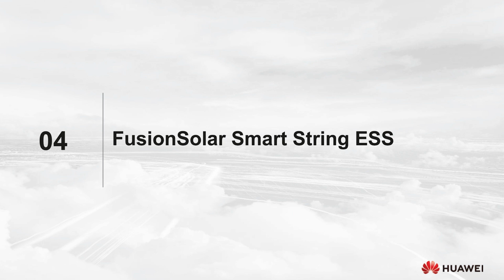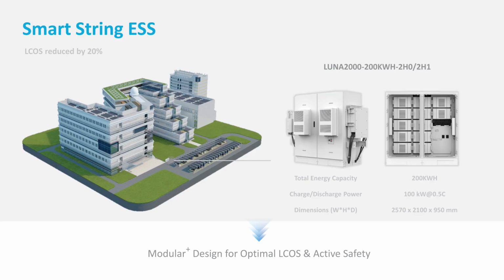Okay, so let's move on to the topic that we are here for today, which is the FusionSolar Smart String ESS. This is a containerized solution. It's 200 kilowatt hours. We call it 200 kilowatt hours, but it's actually 196 kilowatt hours. We've got 12 battery packs in there, which are 16.13 kilowatt hours each, and this is 0.5 C. So we can only do 100 kilowatts in backup, 100 kilowatts for 2 hours.